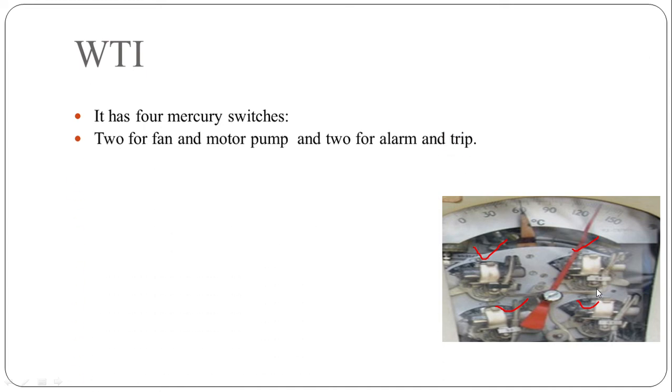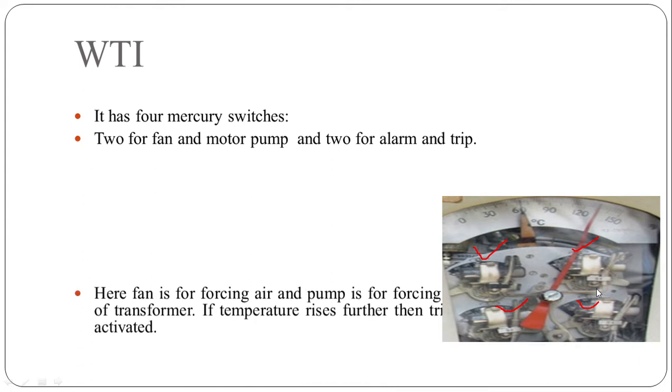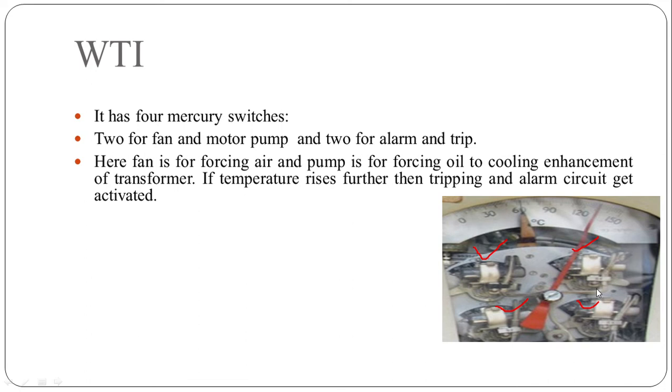Two mercury switches are for fan and motor pump and remaining two are for alarm and trip circuit. Here fan is used for forcing air and pump is used for forcing oil. These fans and pumps are used to enhance the cooling of transformer. If temperature rises further then tripping and alarm circuit get activated. The operation of these switches can be understood by using an example.